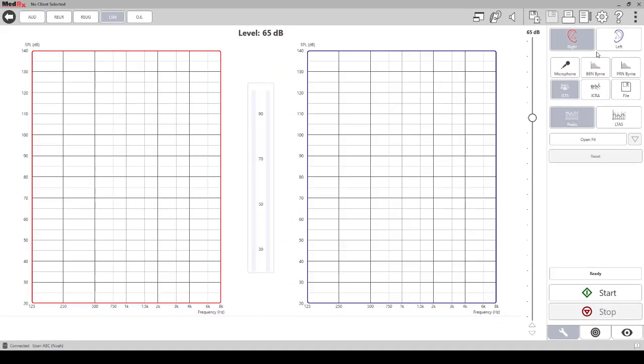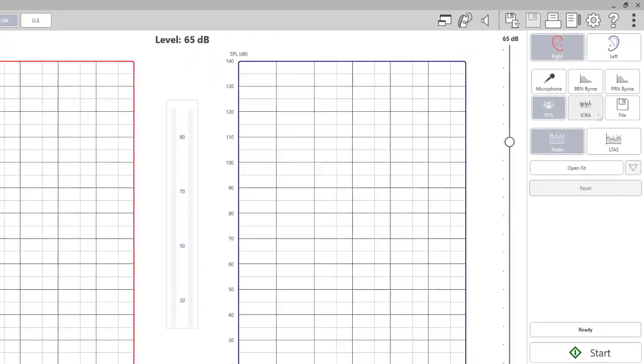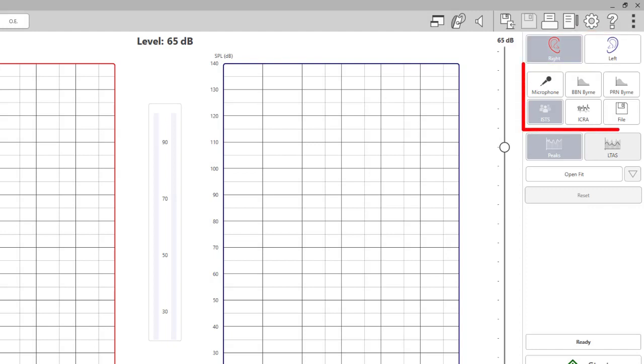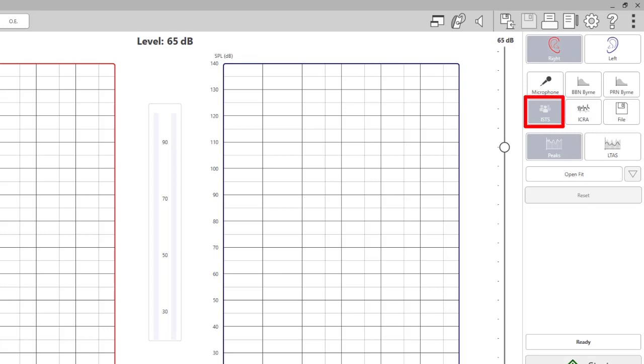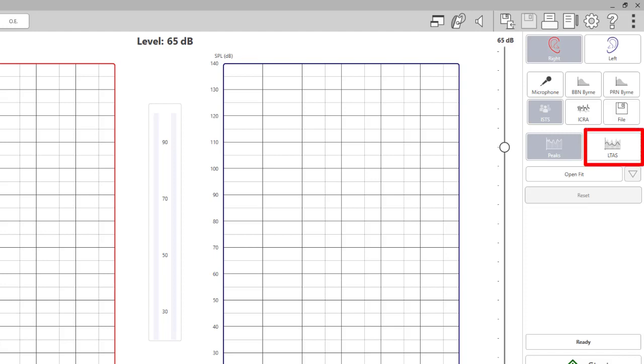Your LSM control panel is on the right side of your screen. Here you will find the following options: right and left ear, stimulus options. Speech is the recommended stimulus for LSM measurements. Appropriate options are ISTS file or live voice. Peaks and LTAS measurements. Peaks will display the measurement curves as the peaks of the measurement. Since speech fluctuates, the curve will represent the loudest the stimulus was for a particular input level. LTAS will display the average of the measurement for a particular input level while the stimulus was running. Open fit function for LSM. This will be discussed further in the LSM training video as it relates to LSM measurements and when it is required.